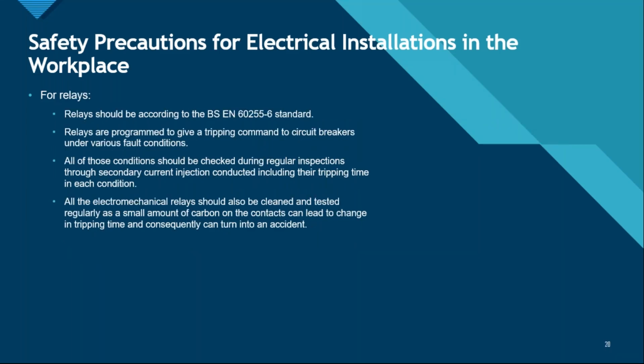For relays, relays should be according to the British standard BS EN 60255. Relays are programmed to give a tripping command to the circuit breakers under various fault conditions. You need to check the electrical drawing. You need to check what the different types of fault conditions are that might happen in an electrical system, and also what the different types of faults are that the relay might be programmed for, and all of those fault conditions need to be tested for regular testing and maintenance.